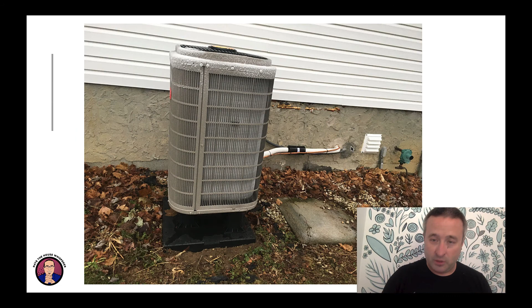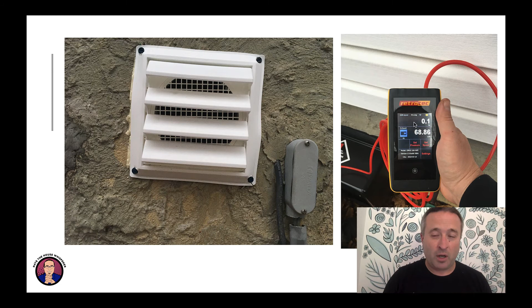See over here, this is the fresh air intake for the badass HVAC. And so I measure what those are. So this is Lucas Coons here holding the flow hood against here, the flow box. And so we were getting about 70 CFM of fresh air. And this is more than you normally see because this system had a little higher return static pressure than most of the systems that we put in.